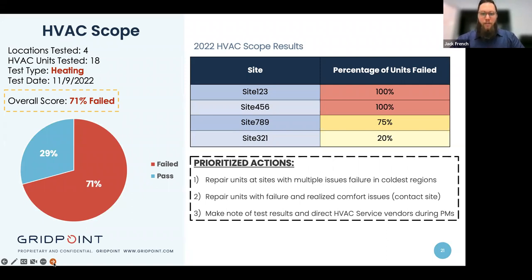So we're coming to this customer saying, here's what you need to do. You need to prioritize first the sites that have the highest percentage of failed units. This is real data, but any identifying information has been masked, so we're calling these site 1, 2, 3 and 4, 5, 6. And for these 2 sites, 100% of their units failed in heat. So we told this customer, you're going to have comfort concerns when you enter heating season because none of these units heat. So we would definitely recommend prioritizing these first, especially if they're in some of the coldest regions.